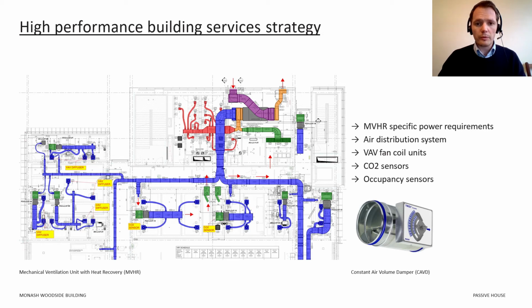That means the pressure drops, starting from the outside air intake all the way through to the outside air supply ducting, back to the return air ducting and discharge through the exhaust air louvers, need to be as low as possible. This required careful consideration during the selection of the mechanical ventilation units with heat recovery. The ducting design was optimized for the smallest pressure drop, while allowing the other building services to be reticulated throughout the building. Low airflow velocities and guide vanes became a critical consideration to reduce the pressure loss across the system.